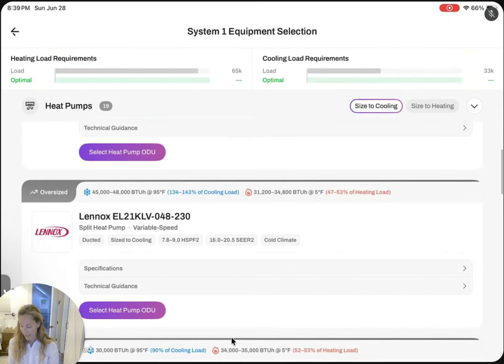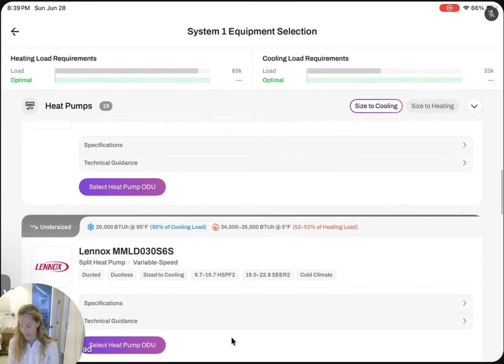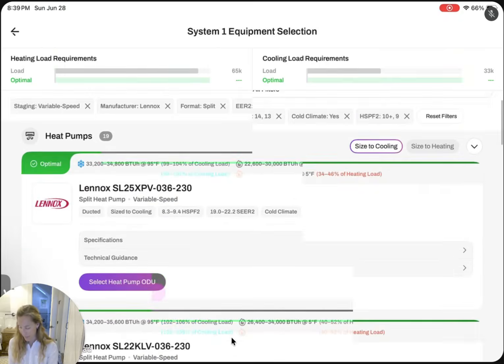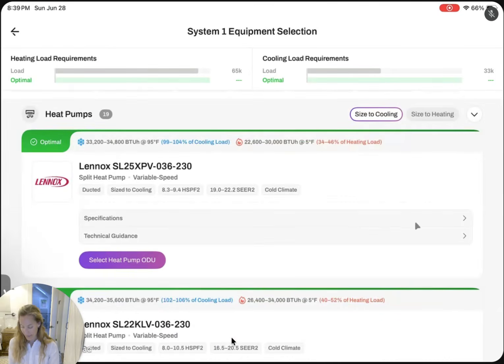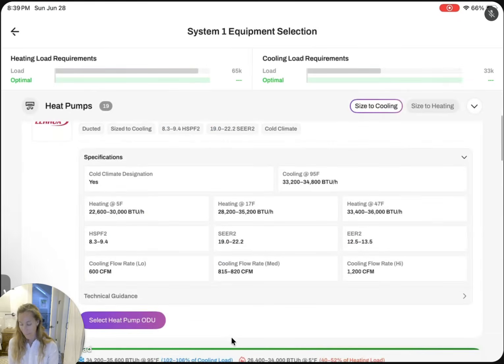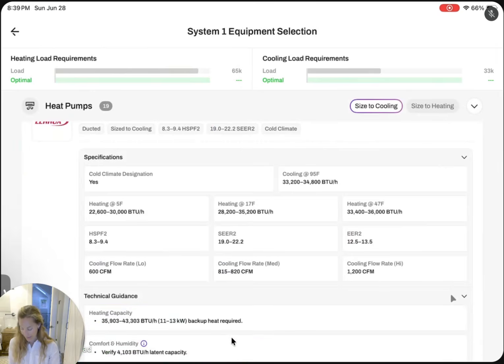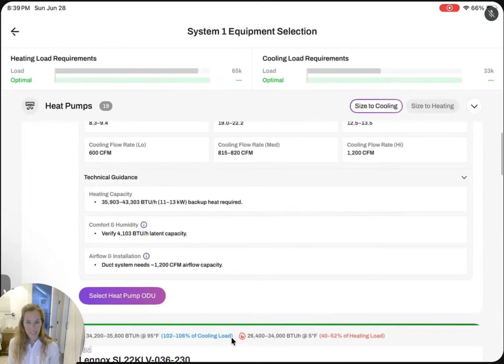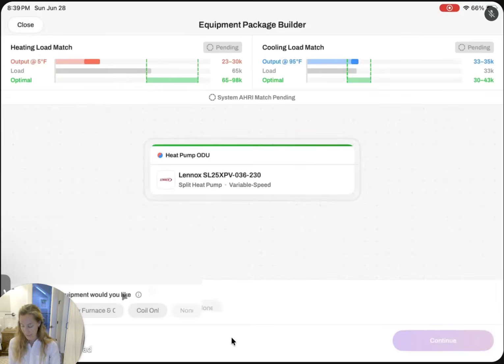We can also see the 4-ton system here is too big, the 2.5 ton is going to be too small. Let's find out a little bit more about this system we're looking to install. We can see all of the AHRI specs. We can also see technical guidance advising how much backup heat would be needed, how much latent capacity removal is needed, and how many CFMs the duct system needs to handle. We're going to select this heat pump ODU.